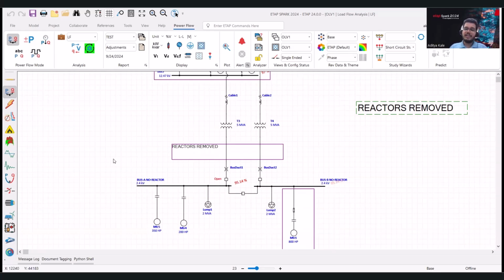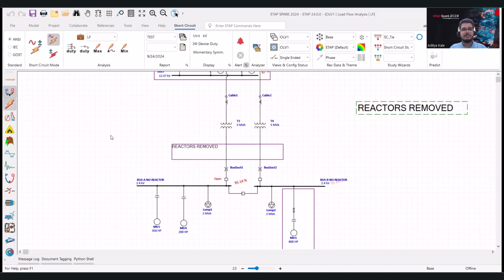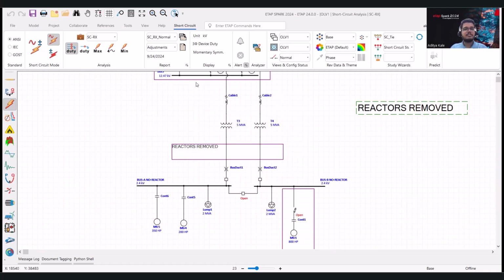However, removing the reactors, we have exposed the substation to high short circuit current. How high? Let's take a look at the numbers. For the short circuit study, to save time, I have set up some scenarios. And I'm just going to use the ETAP study wizard to run through all the set scenarios. The study is running through the normal and the paralleled configuration. So let's take a look at the results.